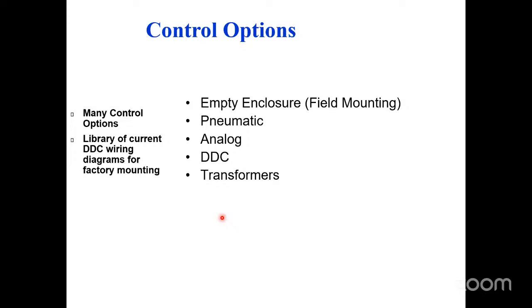You want to mount the controllers for me on my 275 VAV boxes, it'll save me some field labor. And generally speaking, Chicago field labor for an electrician is probably more expensive than wherever the Texas facilities that this is made. You only got 10, 20, 30 VAV boxes and you need them like in 3 weeks. You probably shouldn't mess around with that. Order the VAV boxes, mount your own stuff.